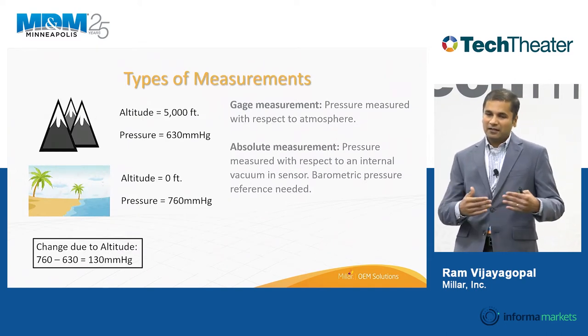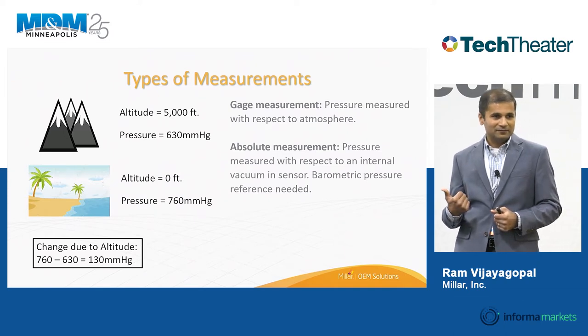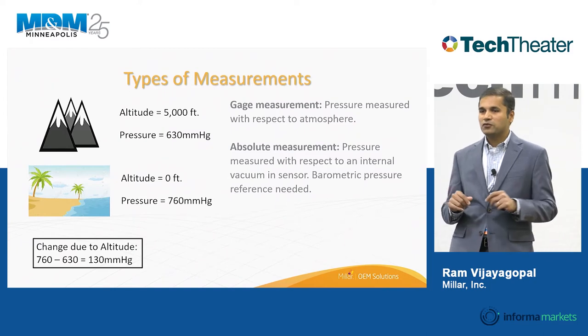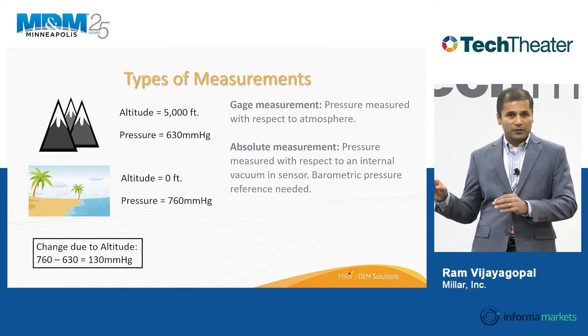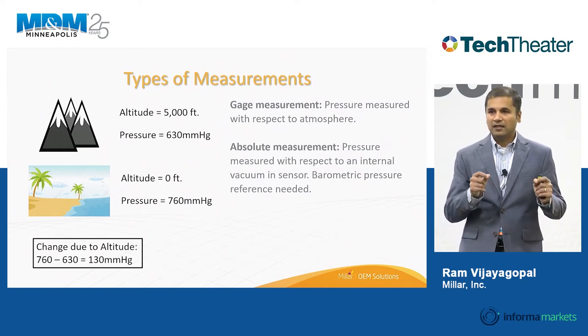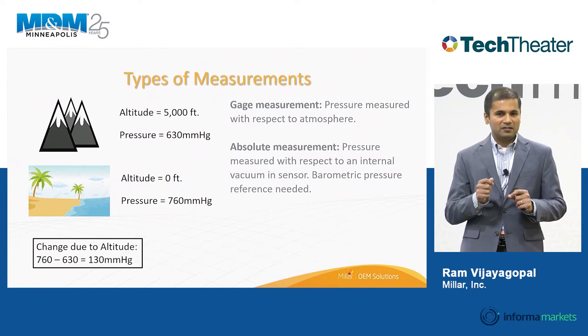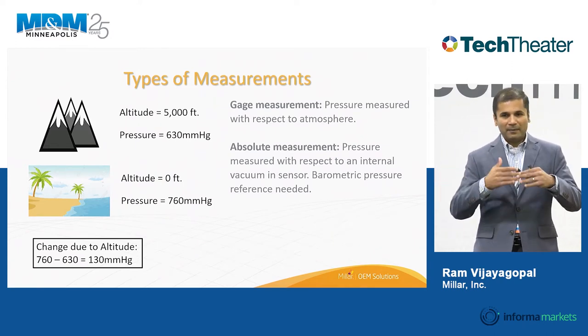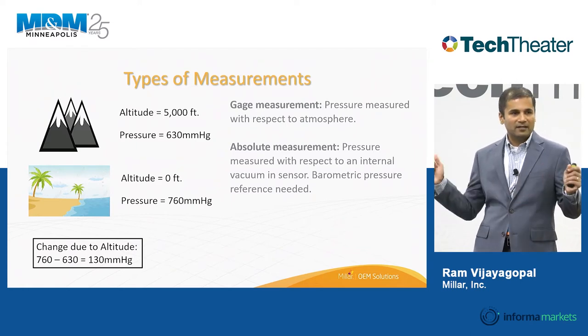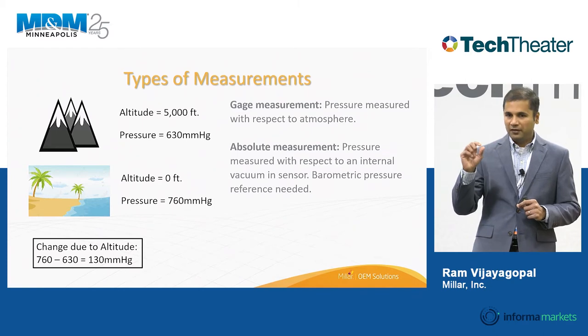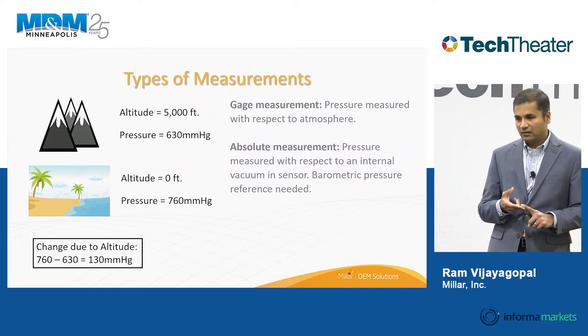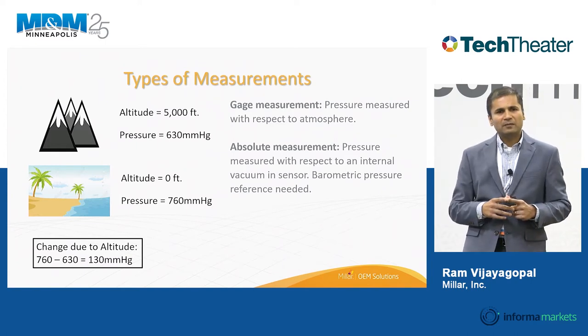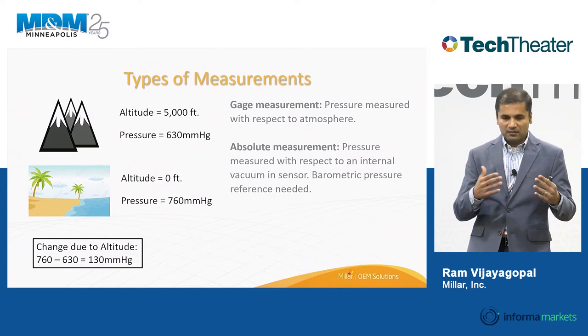When talking about pressure measurements, you're either talking about a gauge measurement or an absolute measurement. A gauge measurement is referenced to atmospheric pressure — simpler to do, but it requires a vent tube to vent the back of the sensor to atmosphere, so it can only be used in applications that allow a wider catheter. If it works for your application, it provides very reliable trending of pressure.